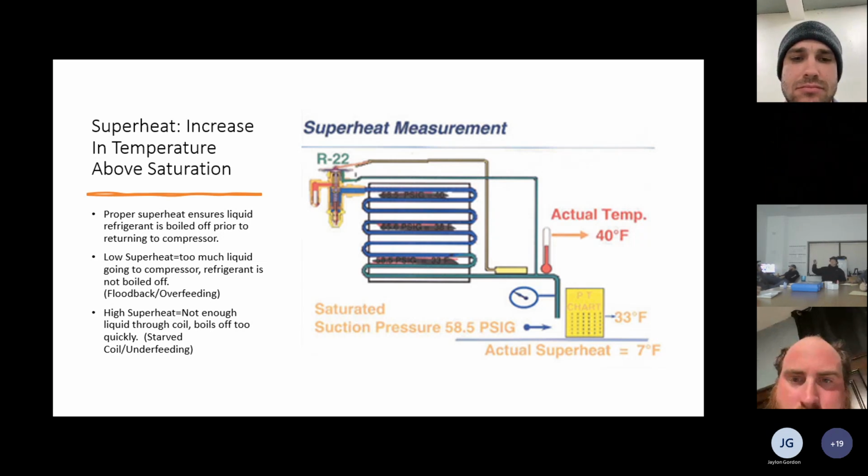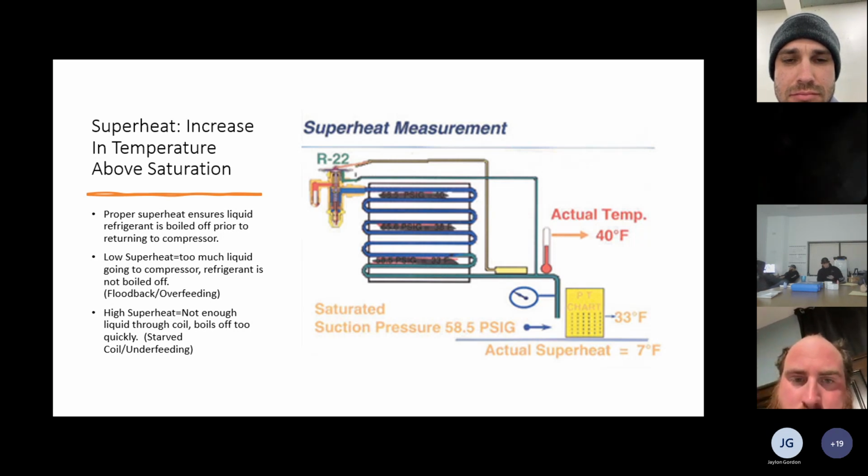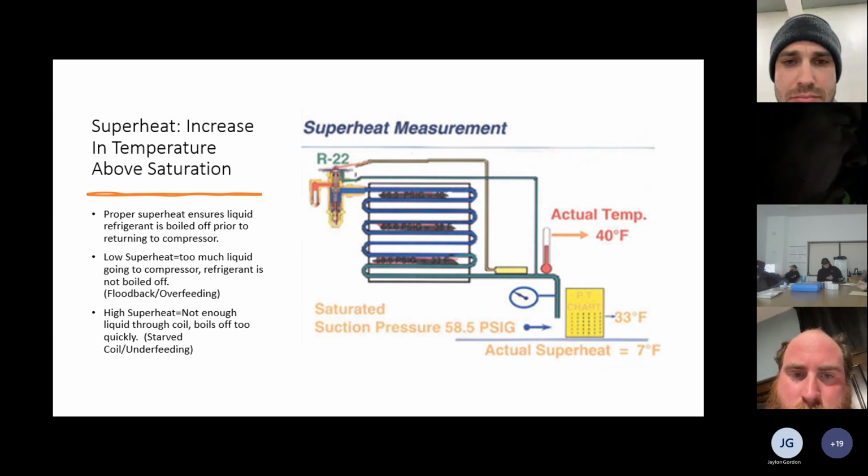All right. A lot of refrigerants nowadays are blends of two, three, four different types of refrigerants. With each one of the refrigerants in these blends, at X pressure, it's going to be a different temperature. When we're talking about digital gauges, the FieldPiece will base the superheat calculation off the midpoint of that glide.